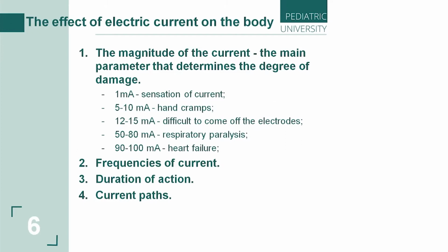The patient, due to various reasons, for example, weakening of the body, the effect of anesthesia, a lack of consciousness, the presence of electrodes on the body, that is, direct inclusion of the patient in an electrical circuit, and etc., finds himself in especially electrically hazardous conditions in comparison with a healthy person. Medical personnel working with medical electronic equipment are also at risk of electric shock, really.